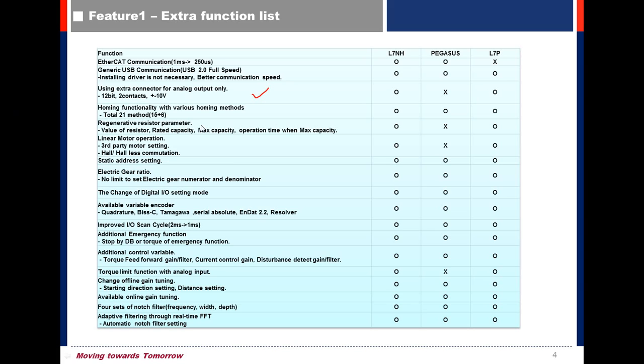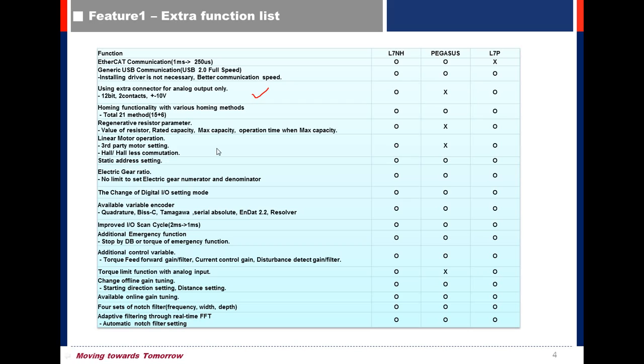But in L7P Drive, you can set the value of resistor rated capacity, max capacity, and operation time during max capacity. So this provides better accurate value of external braking resistor using linear motor including third-party motors.